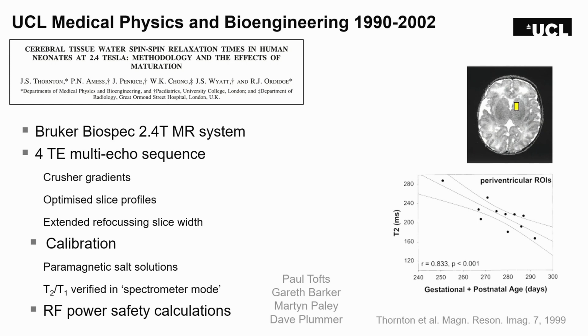And one of the pieces of work that is closest to my heart that I did was to work up T2 relaxometry in the newborn brain. So you can see the image quality is improved. The images were quite good on that system. And I programmed the MRI pulse sequence to collect a multi-echo 4-echo sequence with crusher gradients and optimized slice profiles to get very accurate readouts of the decay rates of the signal, from which we could estimate this parameter called T2, which is essentially sensitive to how watery the brain tissue was.